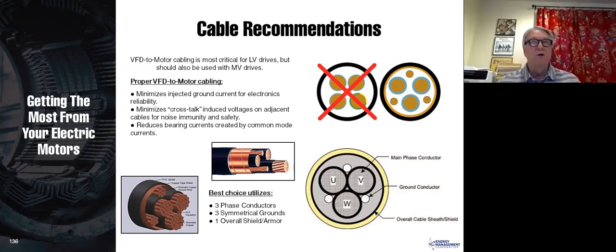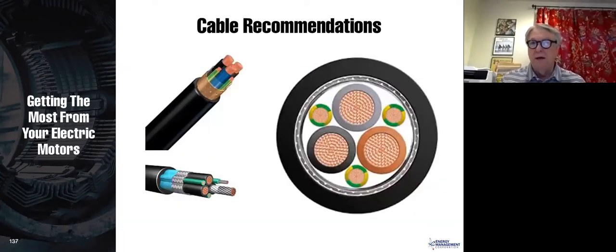ESA recommends you use one on every VFD application. I must tell you that most people don't do that. However, more and more people are beginning to use VFD rated cable. This is only from the VFD to the motor. It is not the cable feeding the VFD. There's no reason to use this on the cable feeding the VFD, only between the VFD and the motor. More people are using this. As more people use it, the price comes down, but there will always be a premium price. I particularly kind of favor this. If I was designing a system, I would add this kind of cable.